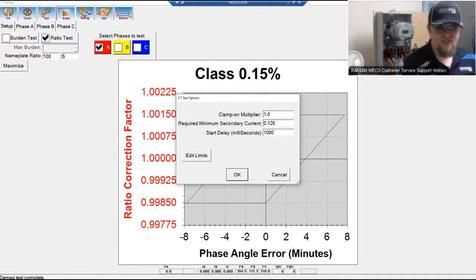Required minimum secondary current: what this does is the RW will not start a test until it sees X amount of current on the secondary. Start delay in milliseconds is when it detects the right amount of primary current. As you'll see when I run this test, it will delay X amount of time before it starts taking readings from both primary and secondary and starting your test. So it gives you a little bit of wiggle room before starting the test and measuring primary and secondary and doing the burden ratio.